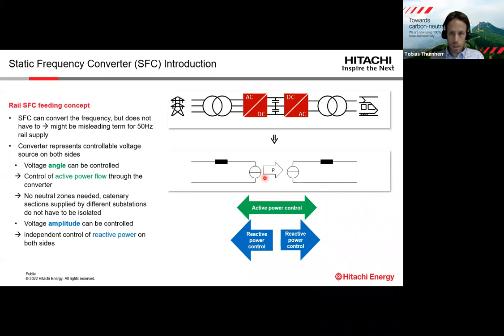the power, because the SFCs have some storage capacity, but that's very limited. So the power flowing in on one side has to be equal to the power flowing out on the other side. And they have a series impedance from a transformer or from an inductance. When I say controllable voltage source, basically we can control the voltage angle, and this means that we can control the active power flow through the converter. And this means that no neutral zones are needed.